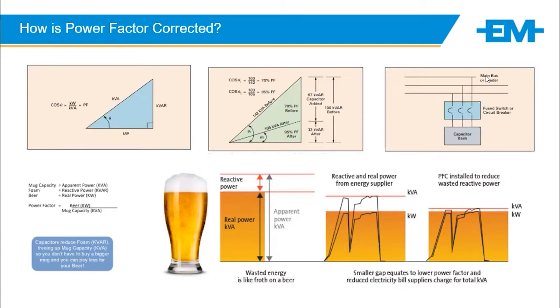So how does this work? On your main bus, you would have a capacitor bank through contactors and the controller sees the requirement and steps in the capacitor bank. Okay. Again, the mug capacity, our beer analogy, my total kVA is my apparent power, and this waste was the reactive. This is what the supplier saw. He saw a reactive and real from the energy supplier, so he charged me on both. I introduced power factor correction, and I brought kVA closer to kilowatts. Okay.